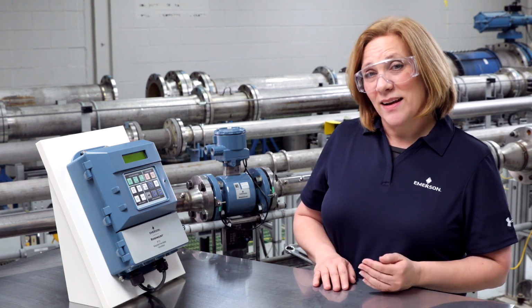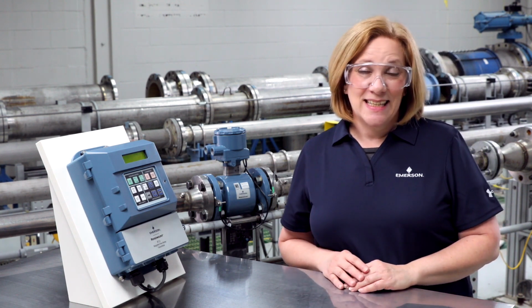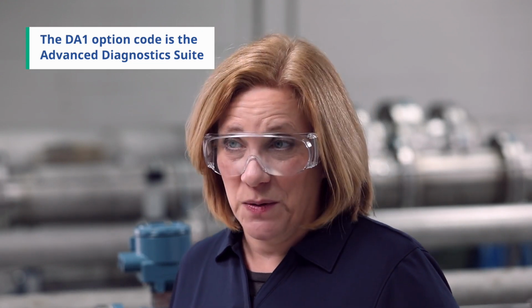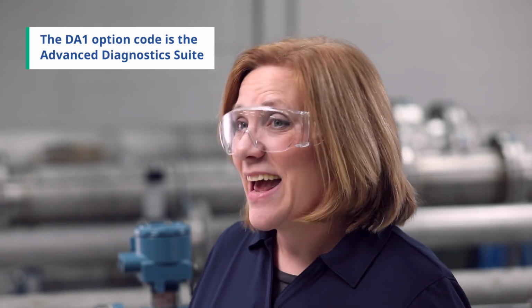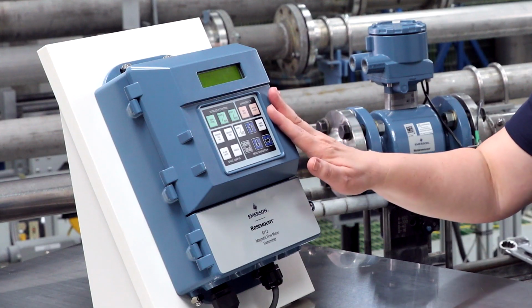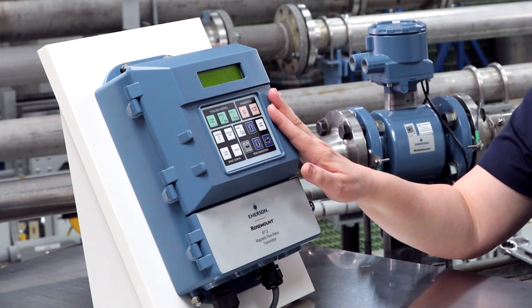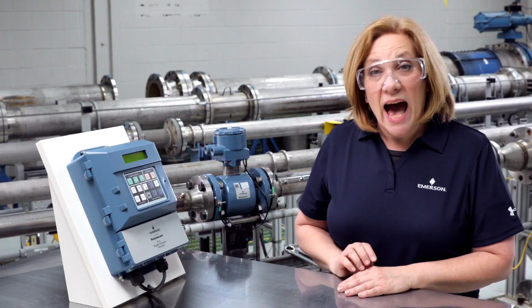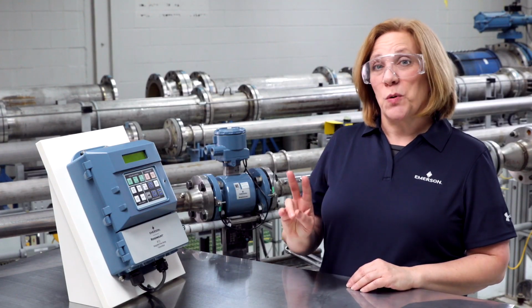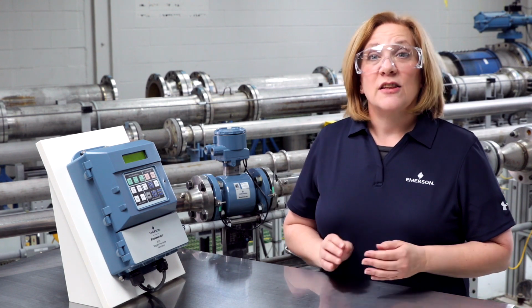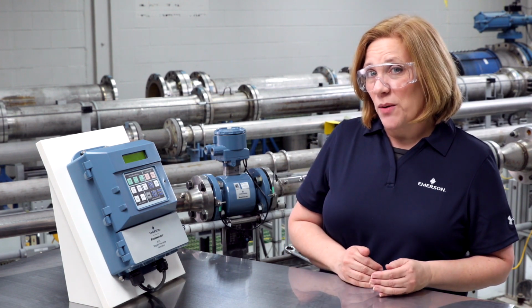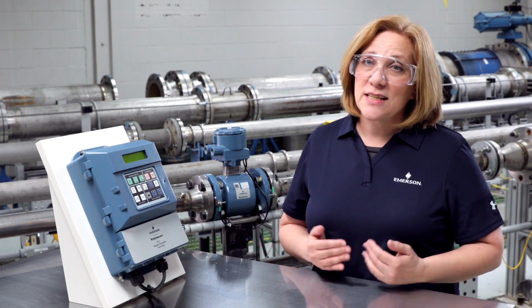They are the DA1 and DA2 option codes. The DA1 option code is the advanced diagnostic suite, which includes high process noise detection and coated electrode detection. You can access these diagnostics through the diagnostic button on the upper right corner of the local operator interface. The high process noise diagnostic has two read-only parameters, the 5 Hz signal-to-noise ratio and the 37 Hz signal-to-noise ratio. These measure the signal strength relative to the amount of process noise.